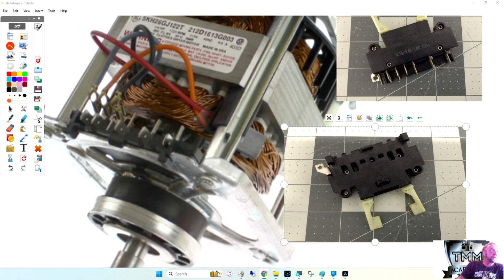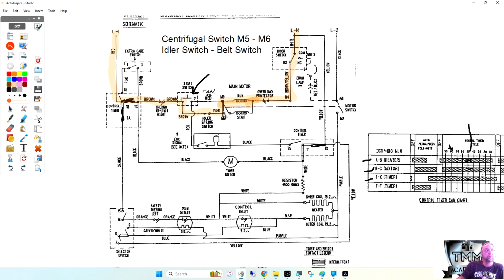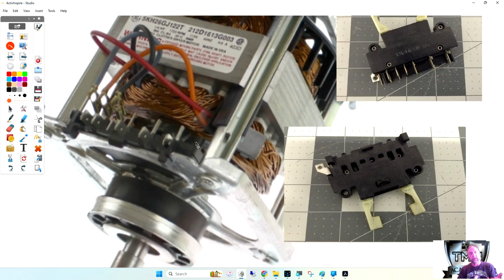So in order to check 5 and 6, according to the diagram, the only time this would be closed is when the motor is running. And when you're testing the motor, there's no power, so you have to move this, which makes it think the motor's running. Does that make sense? So you're going to put your meter lead on 5 and 6 here, or vice versa. I don't remember which one it was the way it's laid out. But then you reach down and you press the lever. When you press it, it should close, and when you let go, it opens.